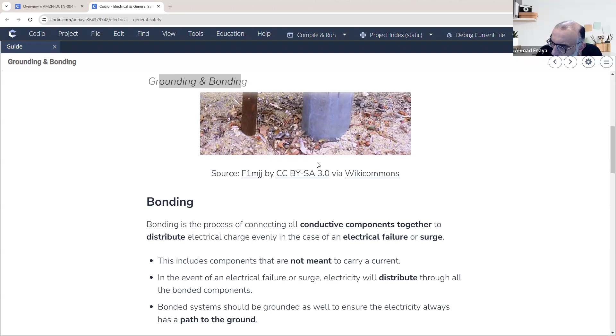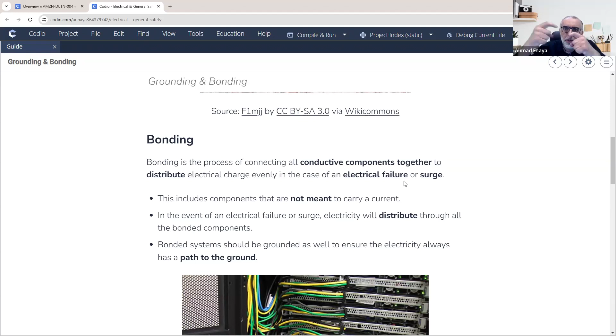And all this is well documented in any installation guide. Any installation guide for any equipment includes the instructions for grounding and the instructions for bonding. All these instructions are listed. Everything that has electricity should be connected to the ground, and anything that is non-electrical carrying should be bonded together. So all conductive components should be connected together to make sure they are at the same electrical potential level. So there is no surge between them, there is no voltage difference between them.